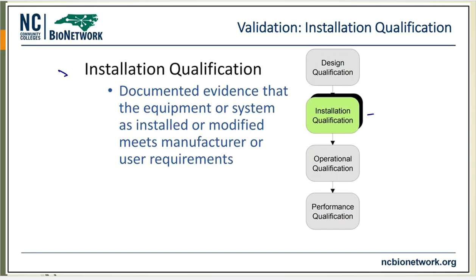So when I order the instrument, and this often comes second, when it arrives, installation qualification is often going to be done. And this is called IQ. That is the abbreviation that we use for that, because very often we are present. We see this happening. So even in the laboratory setting, if in the analytical lab, for you Chemtech people and your biotech people and so forth, if you're in the lab and there's a new instrument that was ordered and it arrives in a box, then that instrument manufacturer will often show up and they will install that piece of equipment for you.